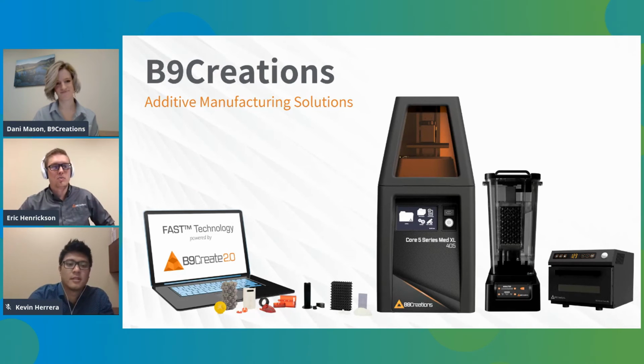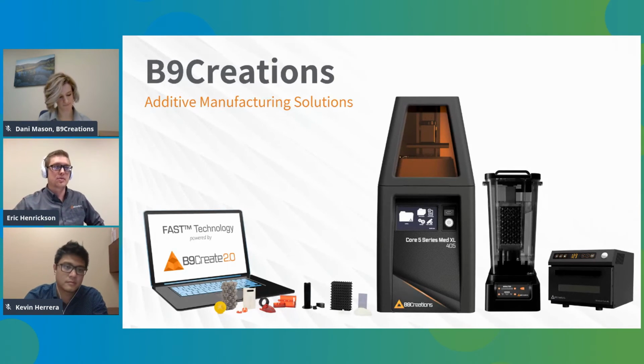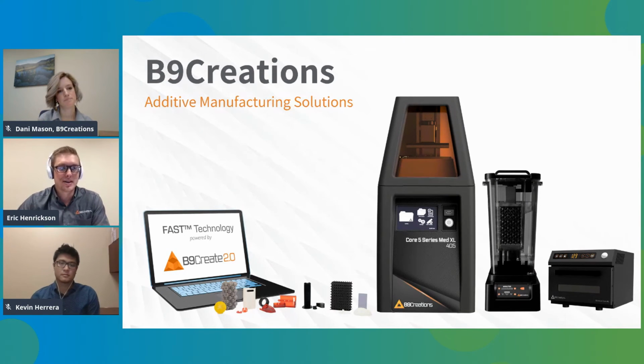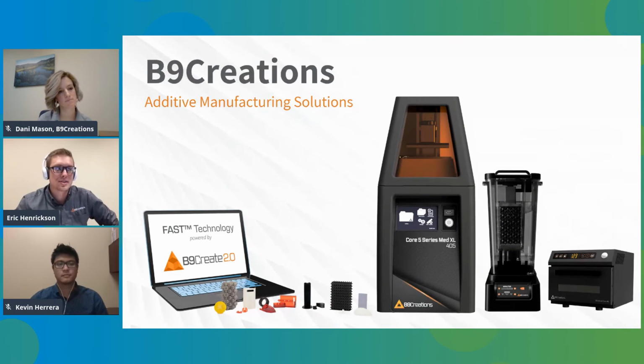Yeah, for sure. We obviously are a 3D printer manufacturer, right? For the medical space, specifically what we have to offer is our new B9 Core 5 Series Med XL. This device is available in both 405 nanometer and 385 nanometer light sources. The build area is approximately 70 millimeters by 125 millimeters. It is an IEC 60601-1 compliant medical device. In terms of applications, you can use it for anything we've just talked about: design, production, end use, medical devices, anatomical modeling, even surgical tools and items like that.